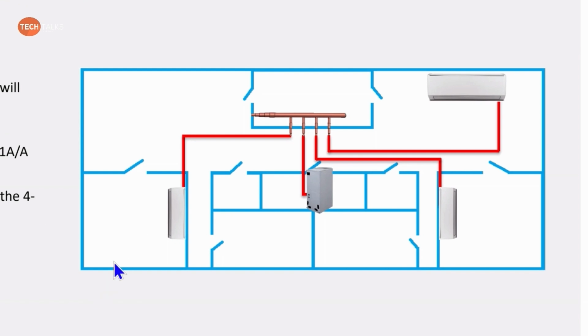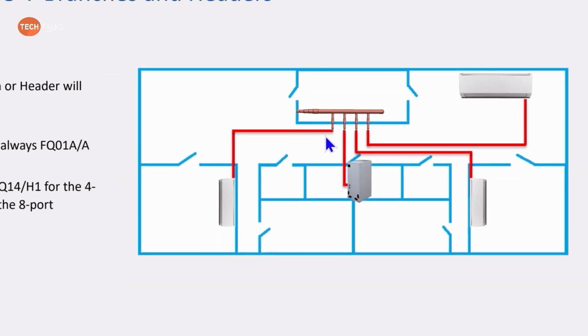So let's say you're going out to the job and you're doing a quick layout for a 4-zone system. Remember what I said, try to keep these pipe sizes under 50 feet so that you're staying to the same size as the indoor units, particularly on the smaller units, because that's the ones that are using the smaller line sets. Like if you're doing an air handler and you're at like 2 ton or above, unless you get to 5 ton, that's going to be a 3/8, 5/8 connection, regardless of your pipe length, as long as we're not exceeding our maximum pipe length, okay? So with that said, you can kind of get a little general layout.